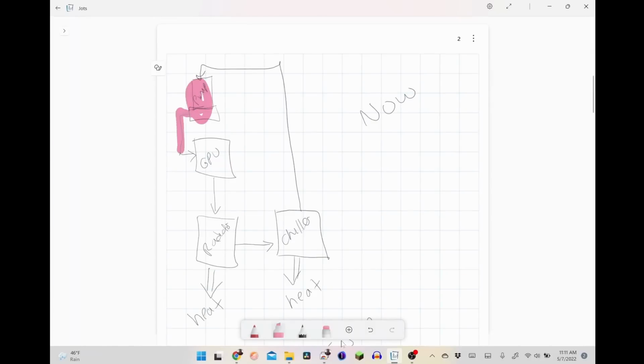It goes from the pump into the GPUs. The cards are being fed with a manifold arrangement, so you basically have one side that's feeding. The cards are in the middle. A pressurized manifold on one side, and then you've got the outbound side coming off. And assuming the cards have a fairly similar amount of flow capability, the system kind of self-balances. It seems to work pretty well.